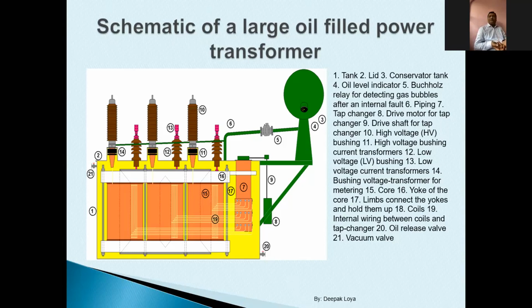Those bad conductors or insulators which we are using in the transformer are of three kinds. One is paper, second is wood, third is oil. Oil has two roles: one is insulation and another is cooling. The fourth type of insulation, which comes under new technologies being used in the transformer, is fiberglass cylinders or fiberglass material. It is a new technology being implemented in the transformer industry.